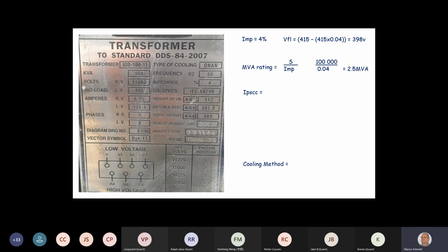Okay? What's HV and LV? High voltage, primary side. LV, low voltage side, secondary side. All right? Okay, guys, what is my prospective short circuit current? So you take it from the LV. Always secondary side. We're always worried about secondary side. Primary side, there's hardly any amps.